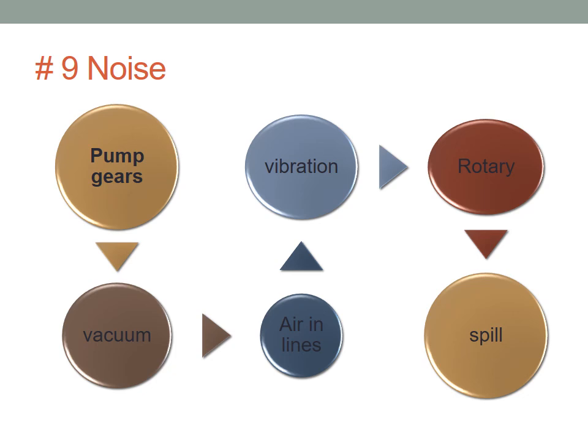If you have noise, check the pump gears, make sure it's not noisy. Try to locate the noise first. Do a vacuum test in the pump. Check for air, because air will cause the fluid inside the pipe to vibrate, and that could be causing vibration. Or it could be a rotary. If anything vibrates, probably a rotary equipment, either a motor, anything that rotates is prone to vibration. So if you have a pump, a fan, a motor, probably it's a problem of rotation and noise. And the noise could be a spill, could be a drop, could be water in the line that keeps rattling whenever flow comes in. So if you have bubbles in your oil and your water line, probably it will make a noise. If you have water in your duct line, probably you have some water spills or stagnation.